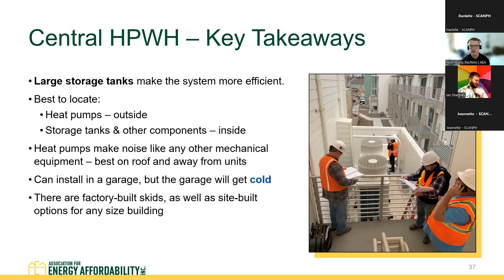These are often referred to as hybrid heat pump water heaters. This one over here has no electric resistance — it's a CO2 heat pump. It operates at full capacity all the way down to about 15 degrees Fahrenheit, and continues at reduced capacity down to about minus 15. It's just a CO2 heat pump here and a storage tank here, with water pipes in between. So if you're concerned about efficiency, this one is basically always going to be the most efficient, but it's also usually the most expensive in terms of installation.